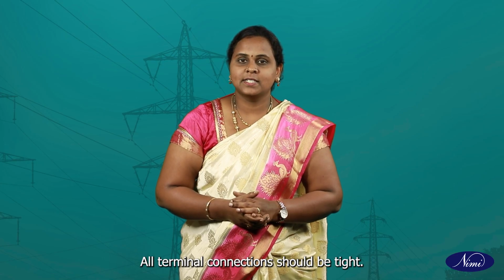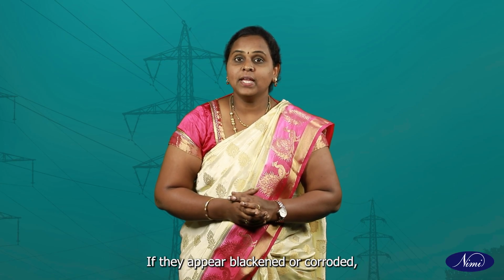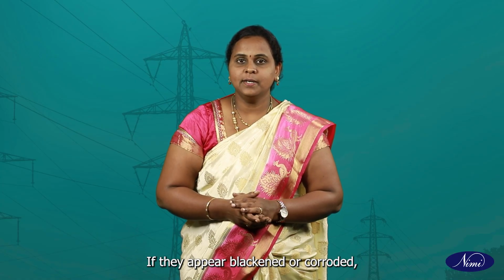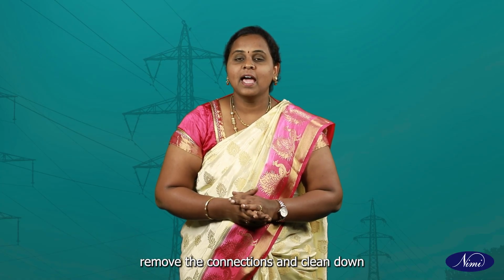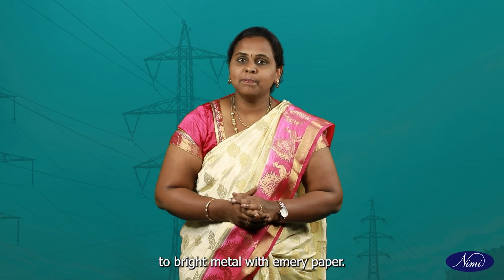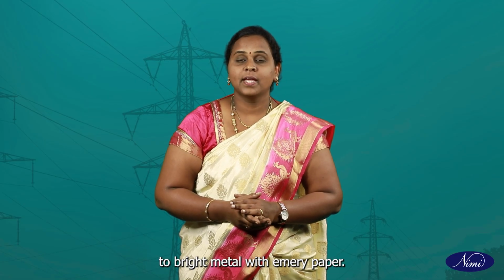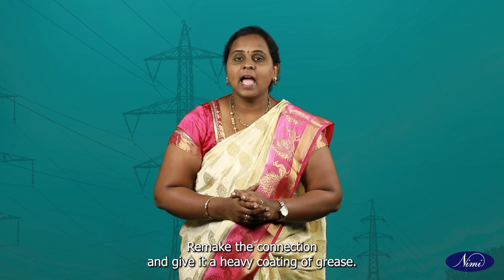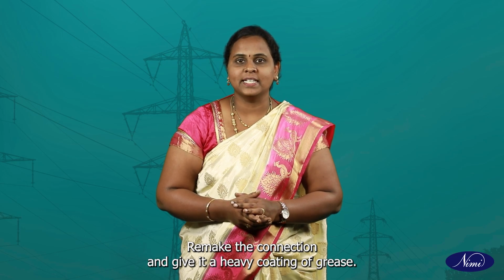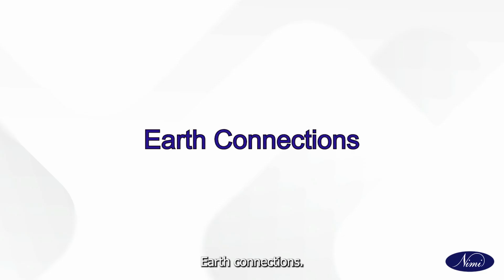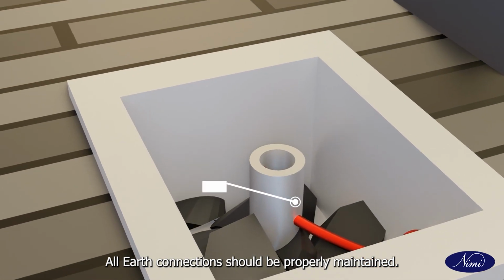External connections. All terminal connections should be tight. If they appear blackened or corroded, remove the connections and clean down to bright metal with emery paper. Remake the connection and give it a heavy coating of grease. Earth connections. All earth connections should be properly maintained.